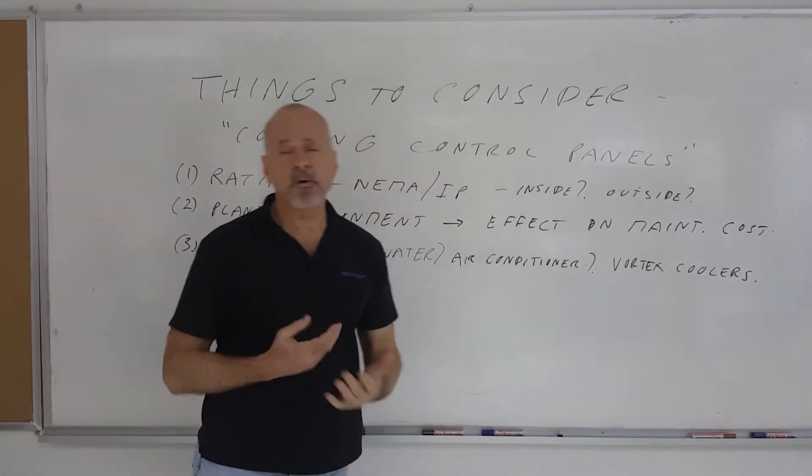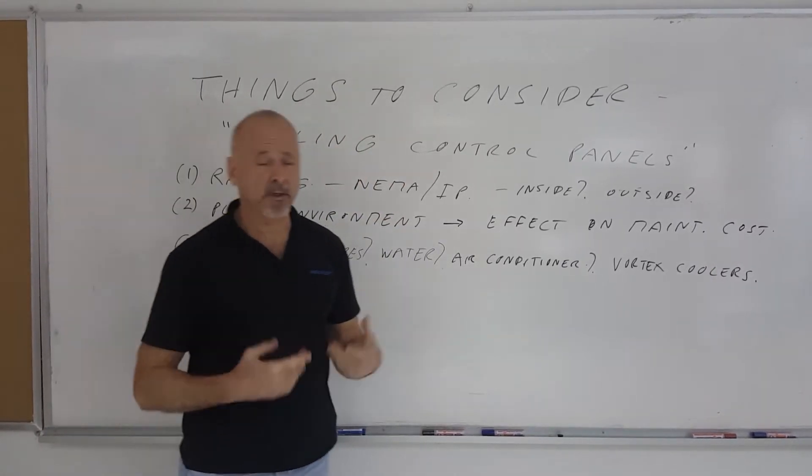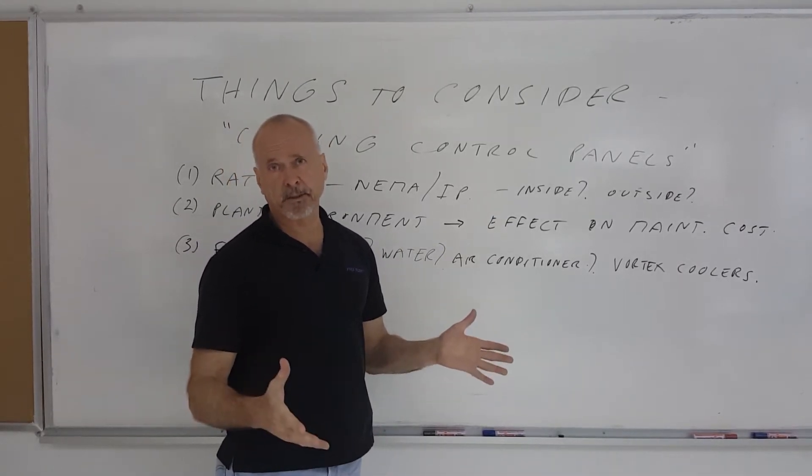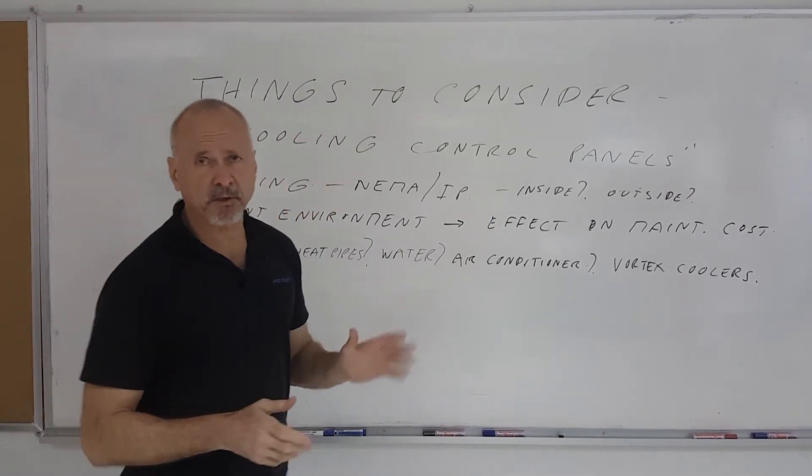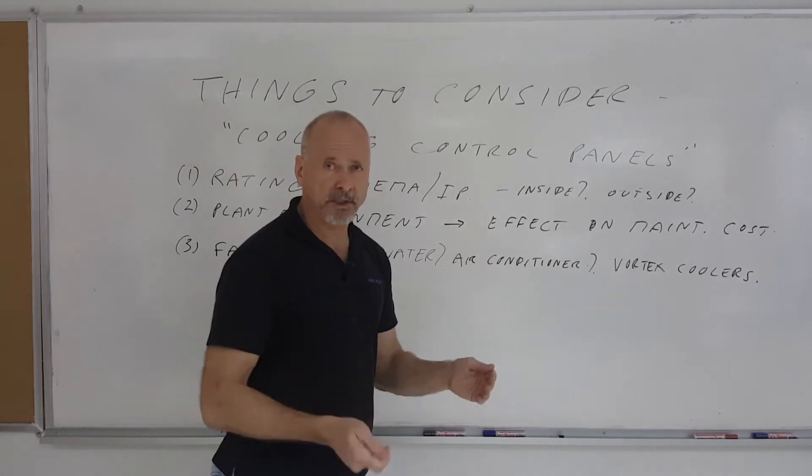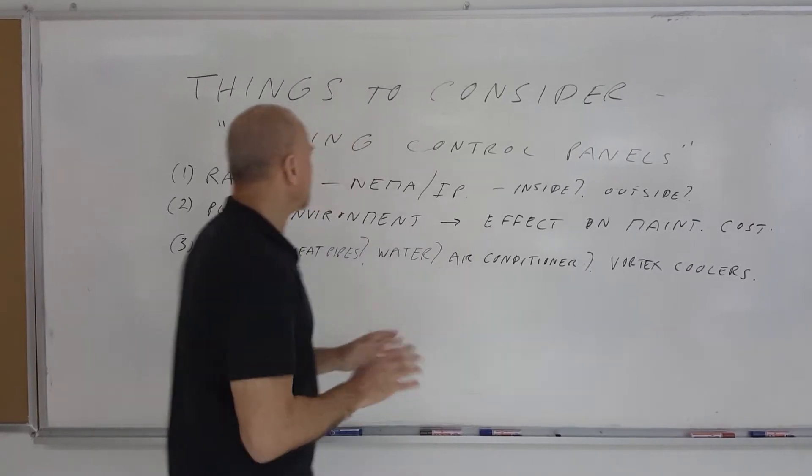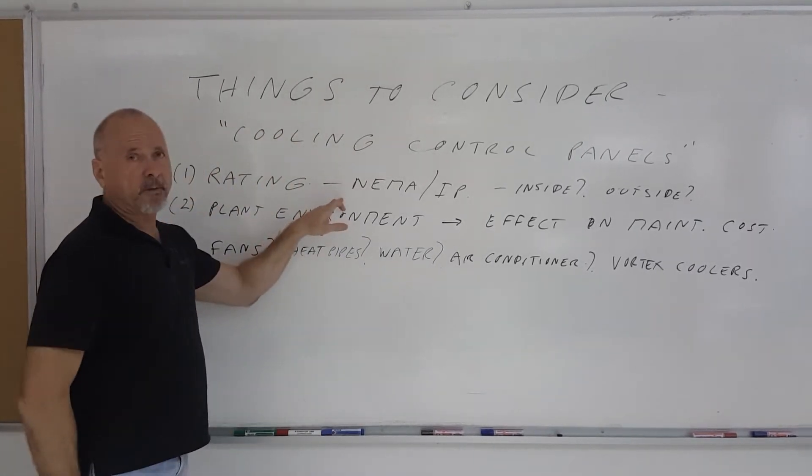For example, a NEMA 4 or IP66 control panel, you can't really put a fan on it because it has to be relatively sealed, because in some situations it has to be subject to a wash down. If you put a fan on there you can get water inside the control panel and that's not good. So the rating is very important.